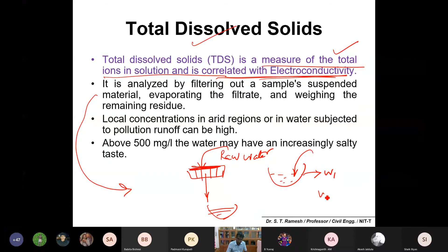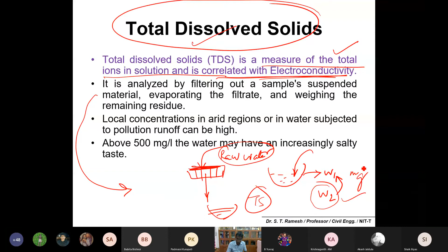That's something important. If you take raw water, without filtration, and do a gravimetric measurement before and after, that will give you total solids. Here it is total dissolved solids. Take a filter, remove the suspended solids, take the filtrate, measure the initial weight of the crucible, and take a known quantity of the water sample and keep it in the hot air oven or water bath. Remove the water, and after removal find the final weight. W2 minus W1 will give you the dissolved solids in grams or milligrams. If you express it per liter, it will be milligram per liter.